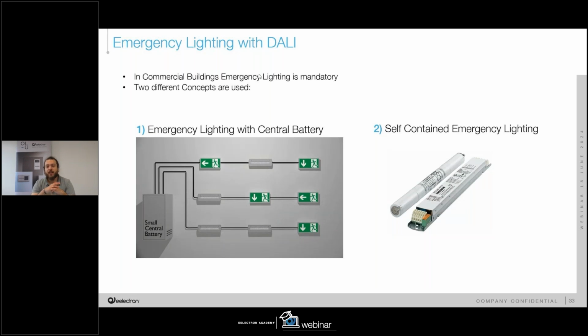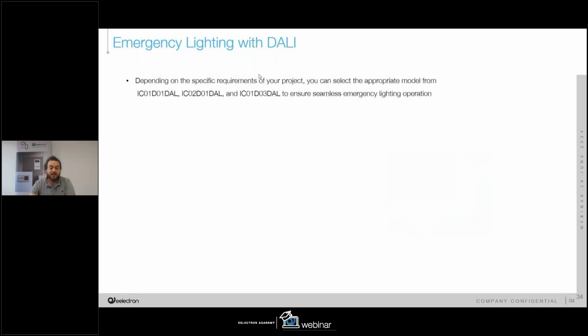So there is a central UPS that will feed every ballast, every light when the mains voltage is dropped. Or we have another application that is with the self-contained emergency lighting system. That means that inside the ballast there is a battery, and each ballast for the emergency lighting system has its own battery. How can we integrate these two kinds of emergency lighting system?